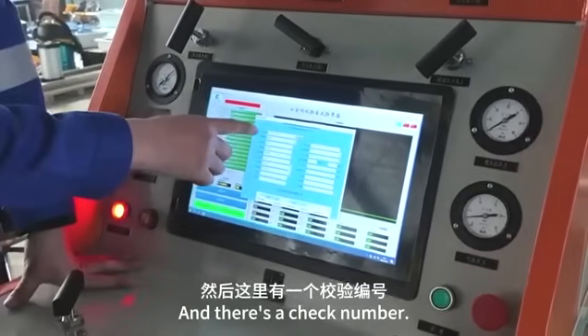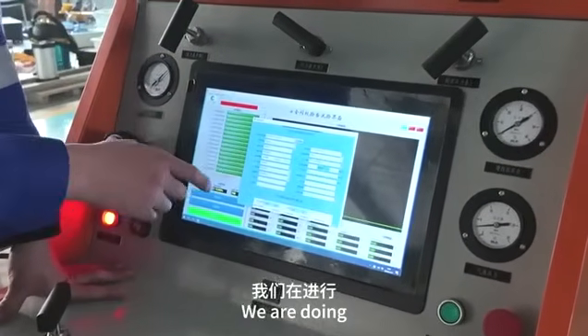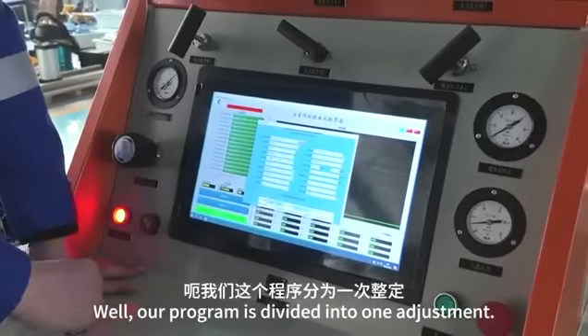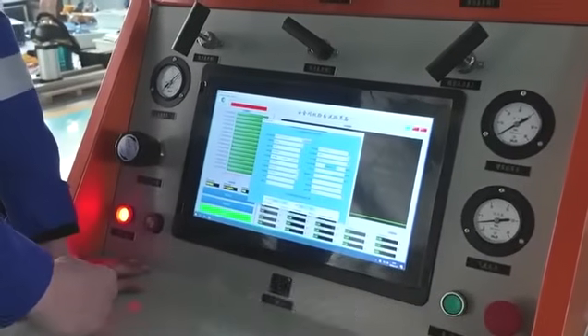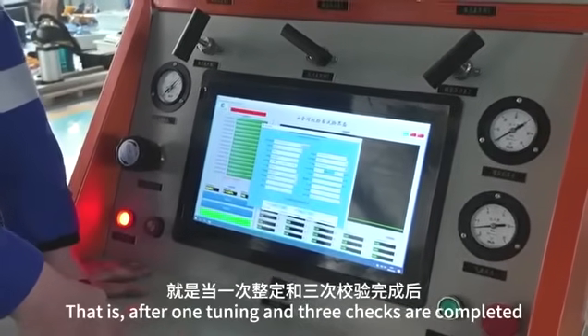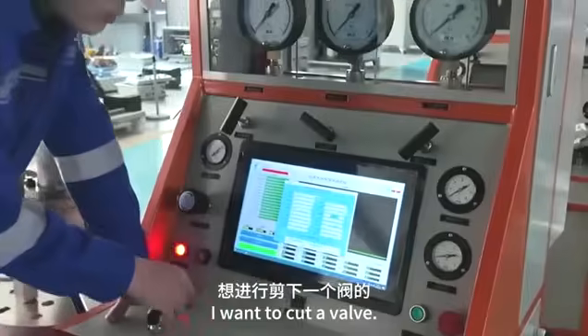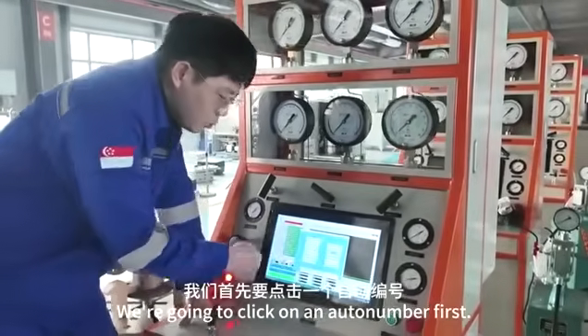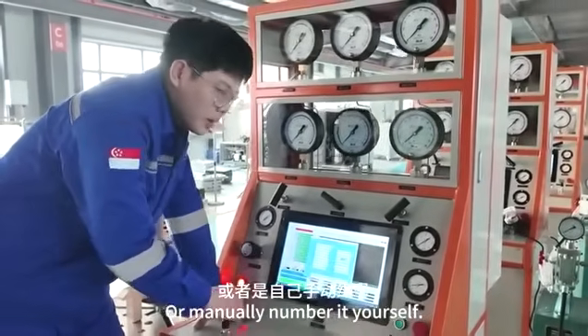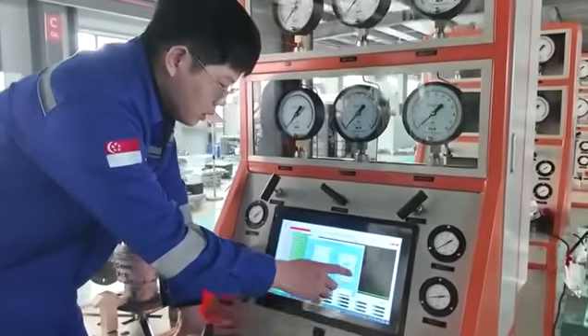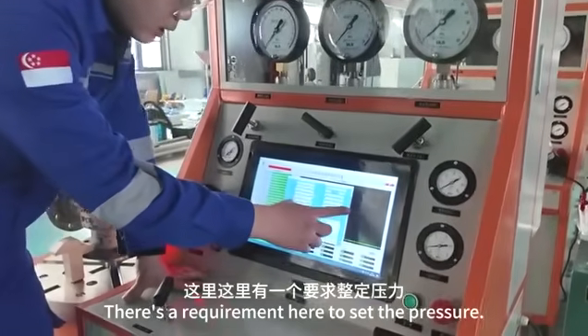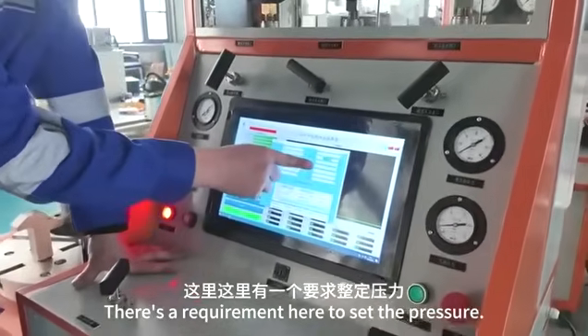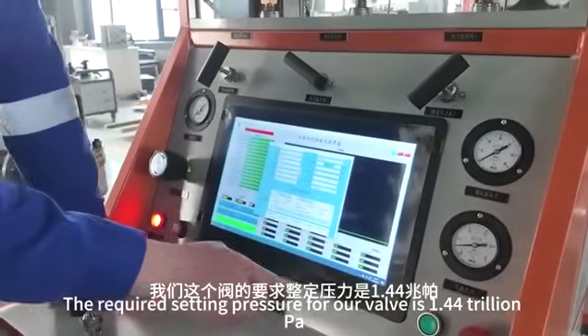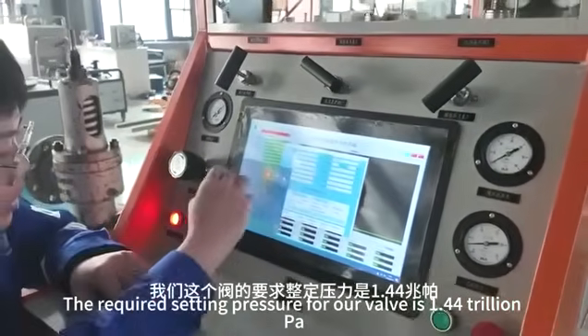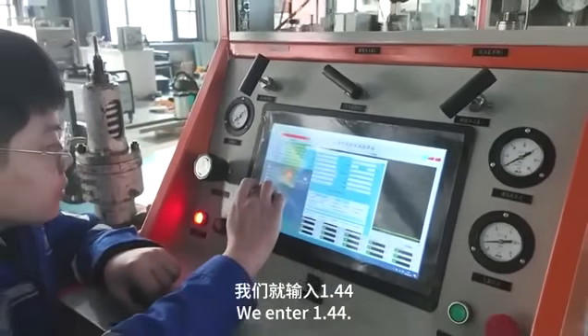And there's a check number. Our program is divided into one adjustment and three checks. That is, after one tuning and 3 checks are completed, I want to cut a valve. We're going to click on an odd number first. We'll manually number it ourselves. It's all okay. Then we pull down. There's a requirement here to set the pressure. The required setting pressure for our valve is 1.44 MPa. We enter 1.44.